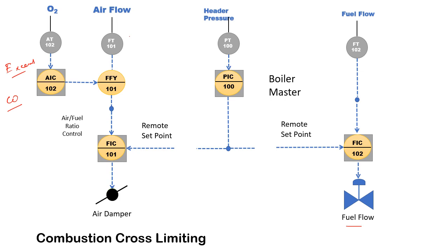What happens is if the amount of fuel in the boiler or furnace is more compared to the air, there is a chance that there will be some unburnt fuel left over in the furnace. It will keep accumulating, and over a period of time this may cause a blast of the boiler. This situation is normally not intended, but due to mistakes like an operator giving wrong set points or issues in loop configuration where certain transmitter readings go beyond expectation, this kind of situation may result.